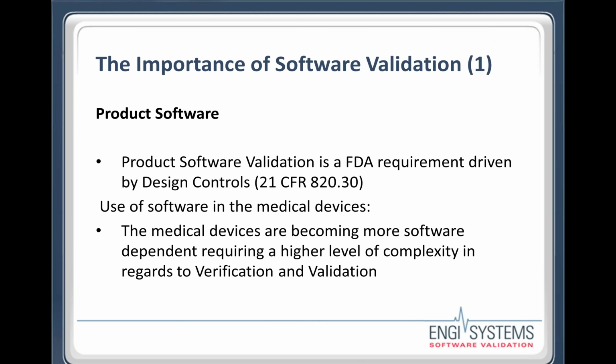The FDA states that software validation is the confirmation by examination and provision of objective evidence that software specifications conform to user needs and intended uses. Software is an integral component of a range of devices that perform critical life-saving functions and basic daily tasks. As patients grow more reliant on computerized devices, the dependability of software is a life or death issue.